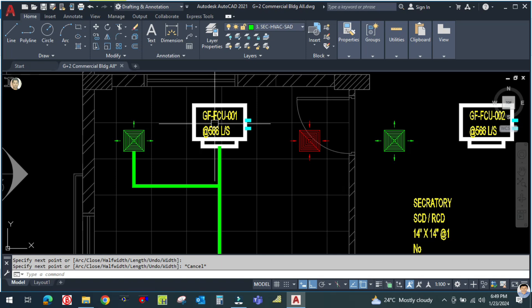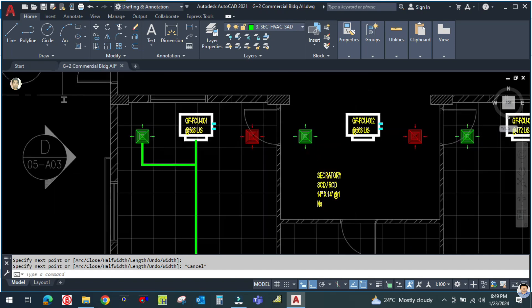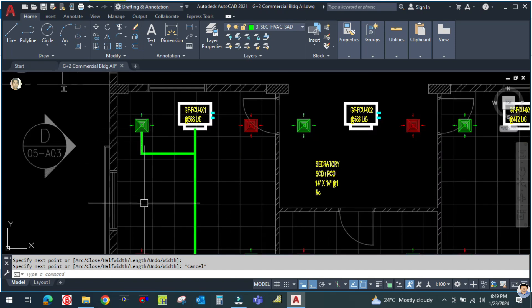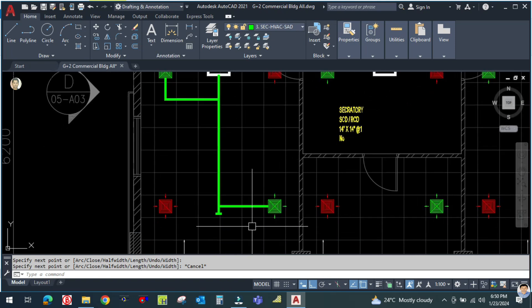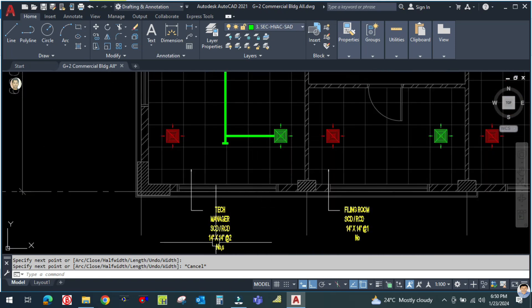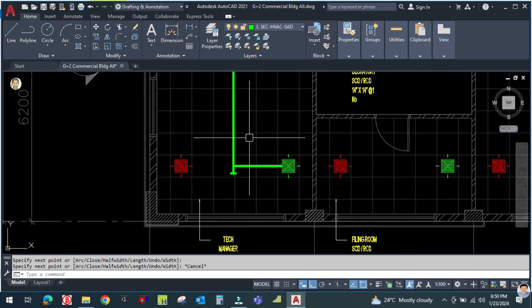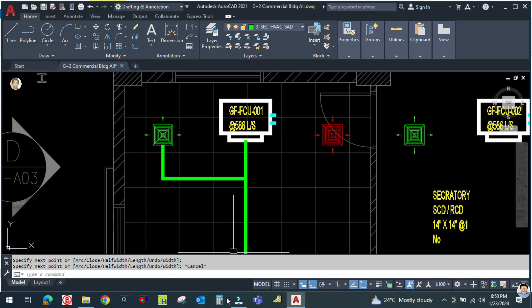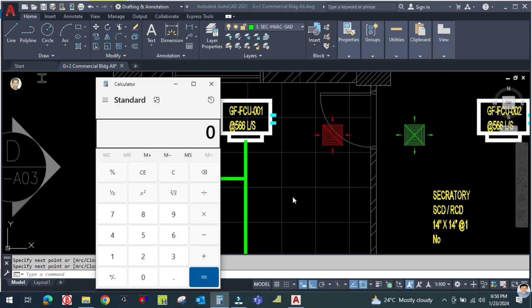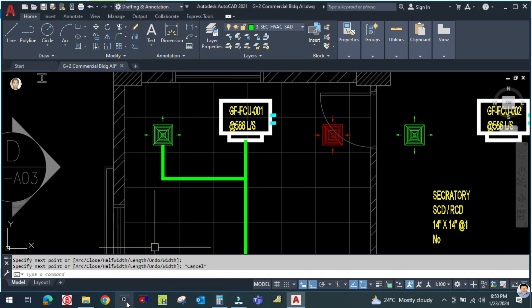The total airflow for this machine is 566 liters per second, which will be divided into two diffusers. Each diffuser CFM will be 283 liters per second. Let me open the duct sizer tool.